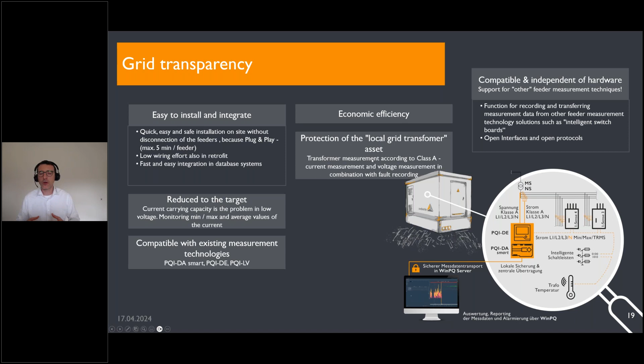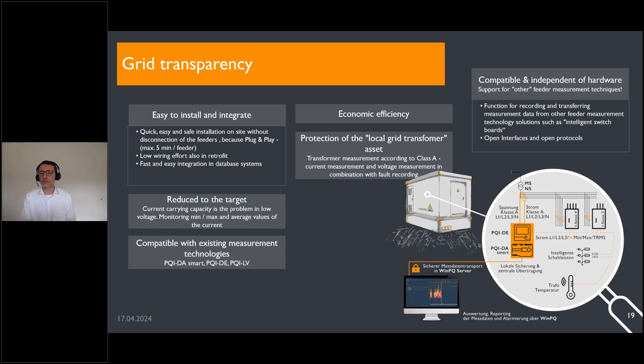It has to be compatible with either our technologies, but also with other technologies which are already installed, and therefore you have to have open interfaces, open protocols, and an opportunity to also collect data from other sources. This is also one big aim, to provide these data to different other data lakes, not only to our own data lake, WinPQ, WebPQ, but also to other third-party data lakes, maybe from the grid operator itself, SCADA systems, for example. And we have to have an opportunity to protect, to monitor the local grid or transformer asset with these high-end power quality measurements.